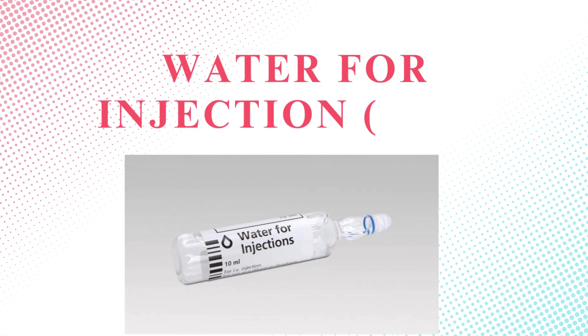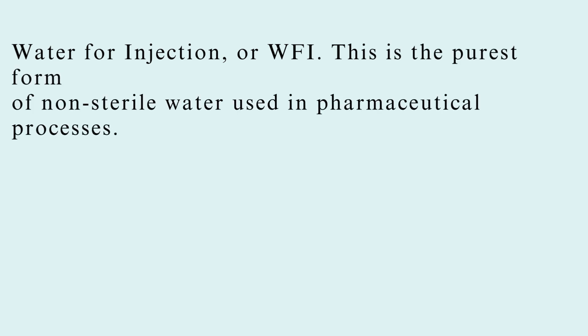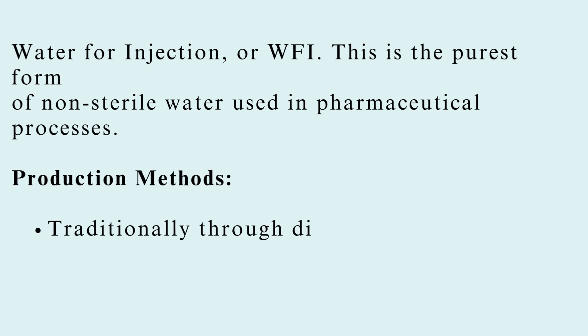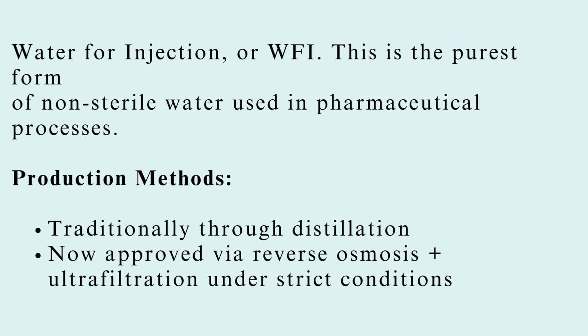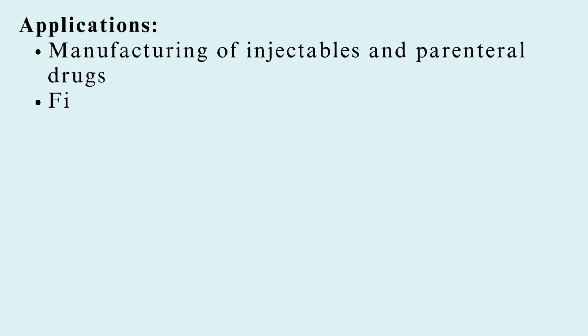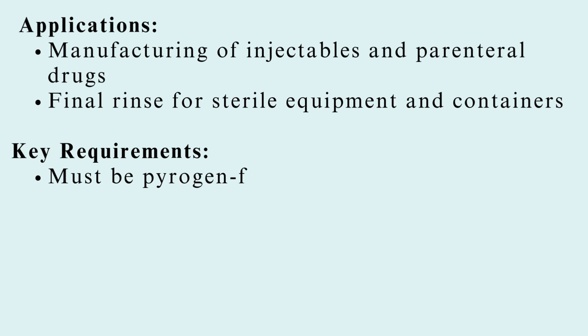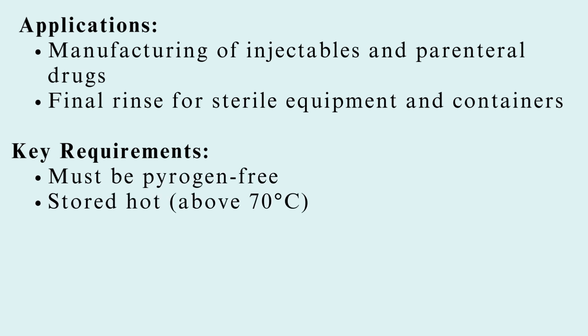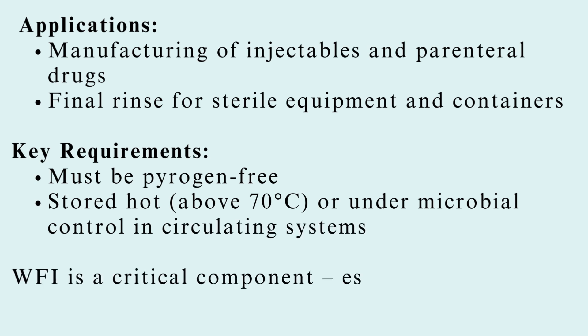Water for injection, or WFI, is the purest form of non-sterile water used in pharmaceutical processes. Traditionally produced through distillation, it is now also approved via reverse osmosis and ultrafiltration under strict conditions. Applications include manufacturing of injectables and parenteral drugs, and final rinse for sterile equipment and containers. Key requirements: it must be pyrogen-free, and stored hot — above 70°C — or under microbial control in circulating systems. WFI is a critical component, especially when it comes to patient safety.